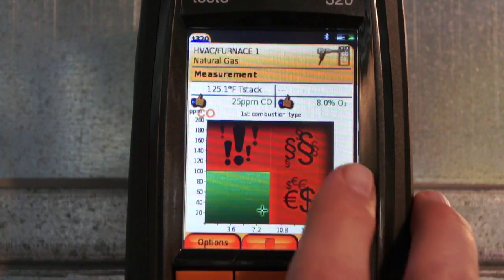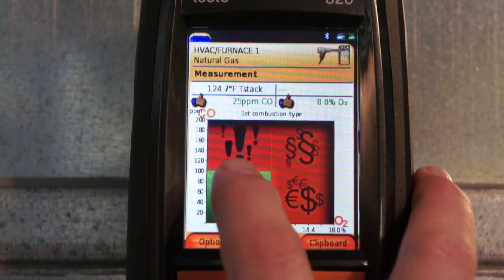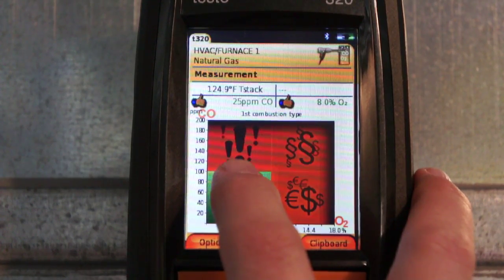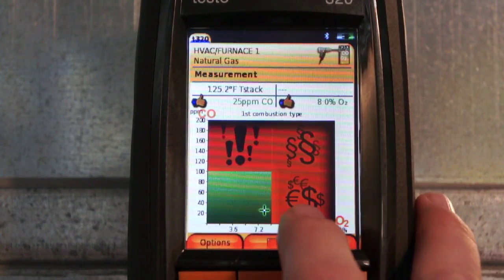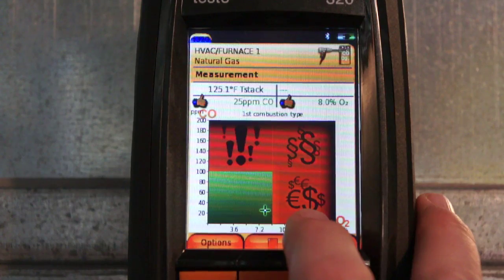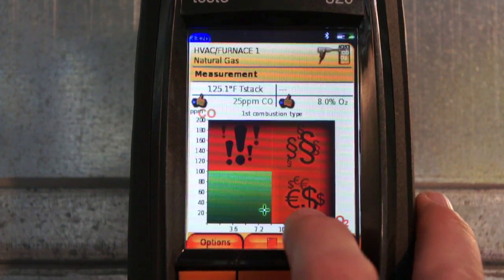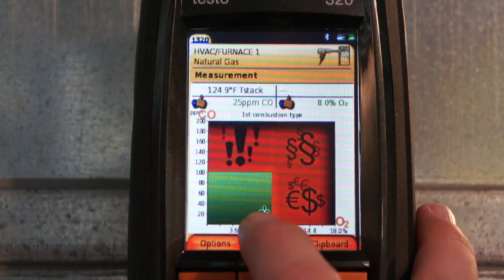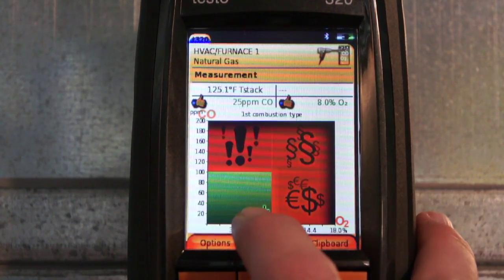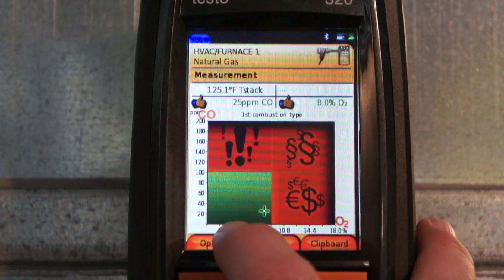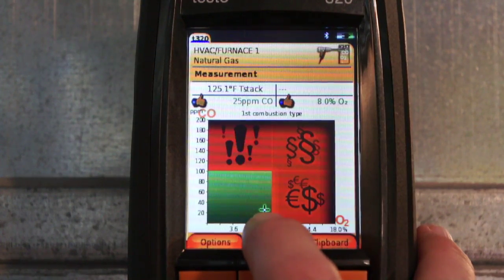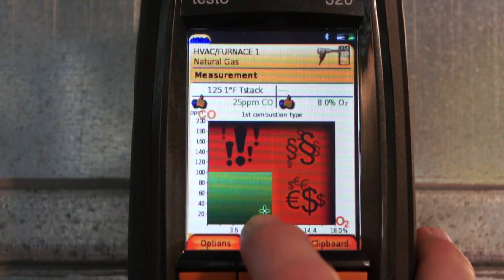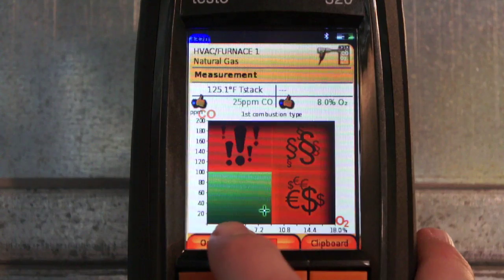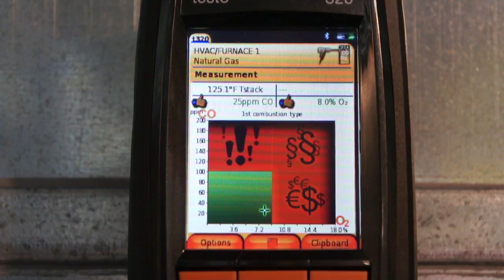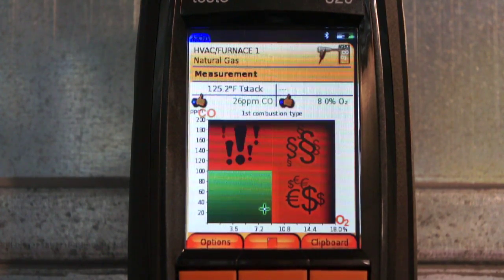Just so you know what's going on in the matrix here, I didn't really cover it in the beginning. I want to just make sure you get this. Up in the exclamation marks means we're getting to the high CO range. Over here into the dollar signs means that we're getting into the high cost range to operate. So over here in the balance point right here, we're at the optimal cost and we're in the optimal safety zone. The further down we get on the CO side, the better off we are. The further in we get on the O2 line, the better off we are, down till we get to the point where we get probably down below 4% O2, which means we're not going to have enough excess air for safe combustion for a residential appliance.